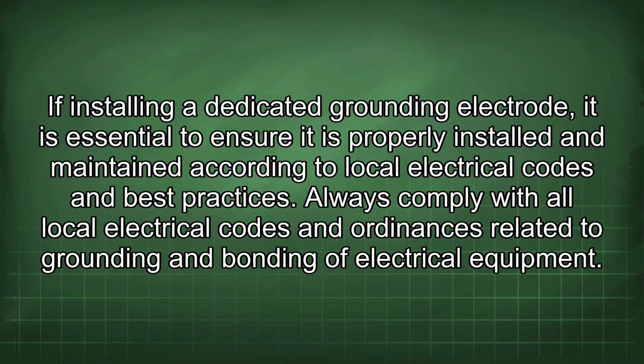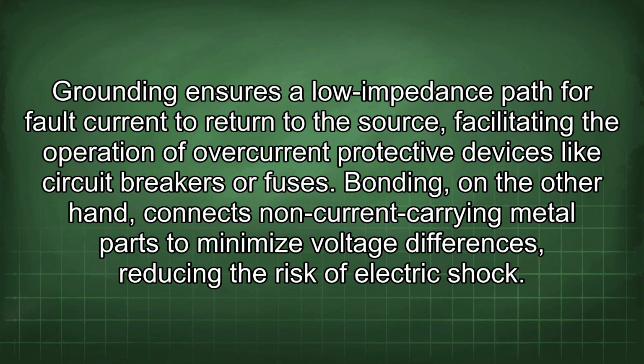If installing a dedicated grounding electrode, it is essential to ensure it is properly installed and maintained according to local electrical codes and best practices. Always comply with all local electrical codes and ordinances related to grounding and bonding of electrical equipment. Grounding ensures a low impedance path for fault current to return to the source, facilitating the operation of overcurrent protective devices like circuit breakers or fuses. Bonding, on the other hand, connects non-current carrying metal parts to minimize voltage differences, reducing the risk of electric shock.